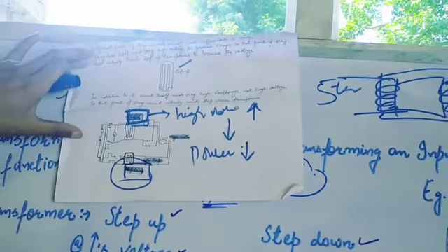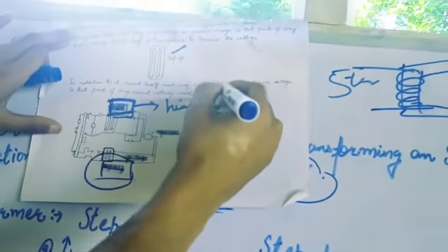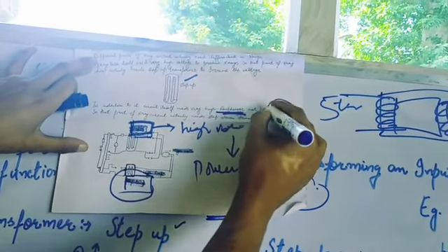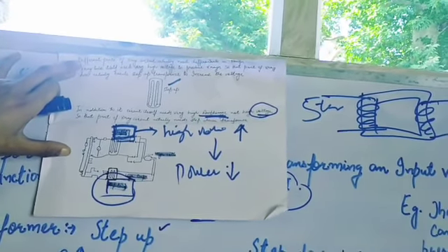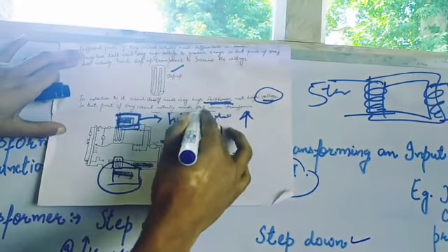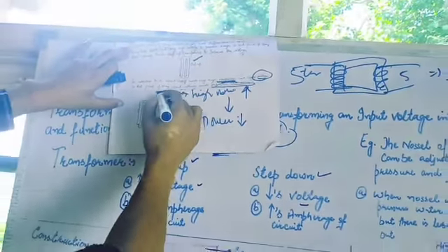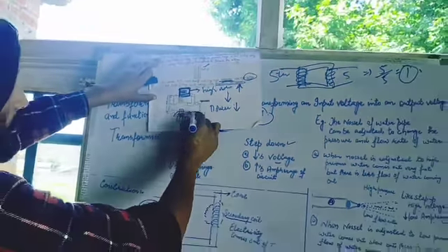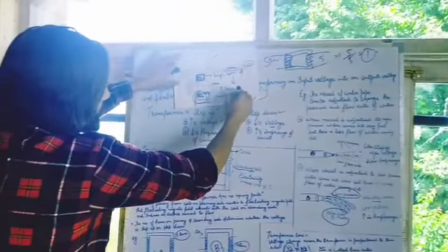So that the X-rays are produced. In addition, the filament circuit needs very high amperage, very high amps, not high voltage. So that part of the circuit needs a step down transformer. Both step up and step down transformers are used, and also auto transformers are used. The auto transformer may be discussed in the next lecture.